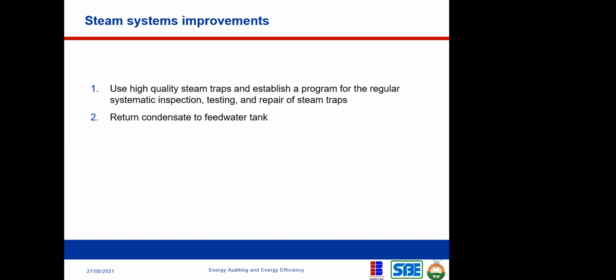So, steam system improvement: use high quality steam traps. Like I said, you need to be very careful about the steam trap. So use high quality steam traps and establish a program of regular systematic inspection. This is very important because you're not seeing what is going on inside of the steam trap. So you need to continuously inspect it to make sure that they are functioning optimally, by inspection, testing, and then repair of steam traps. Then return condensate to feed water.